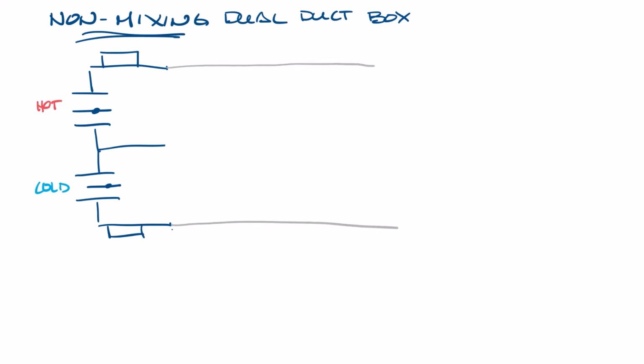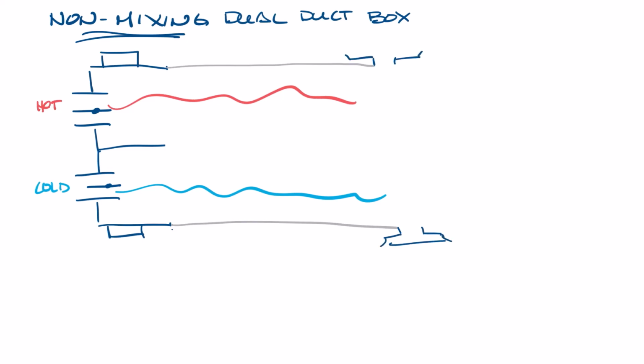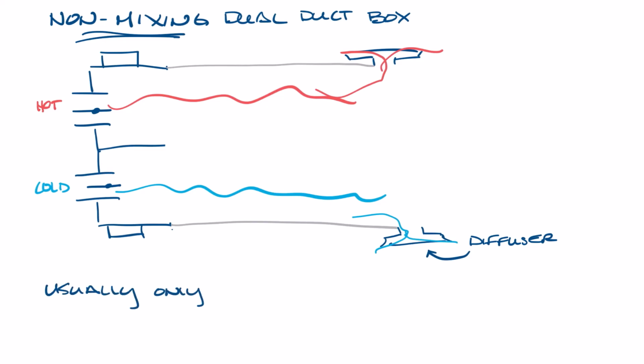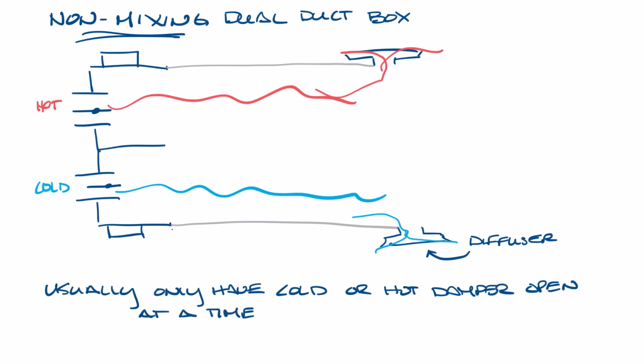Here's the challenge with non-mixing boxes though. Because the hot and cold air streams are not mixed in the box, you could have cold air going down one side of the ductwork and hot air going down the other side of the ductwork if both of the dampers were open. So if I draw in some diffusers here, say that the diffusers are connected to this ductwork a couple feet down the box. This one could get only cold air while the other one gets only hot air. For this reason, non-mixing dual duct boxes often only have cold air or hot air coming at any given time.